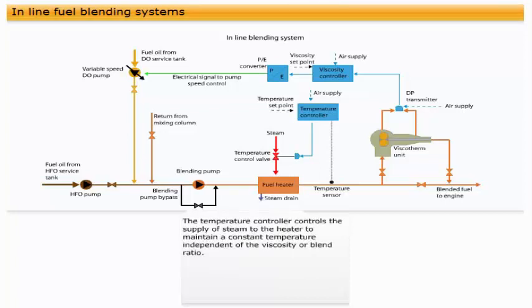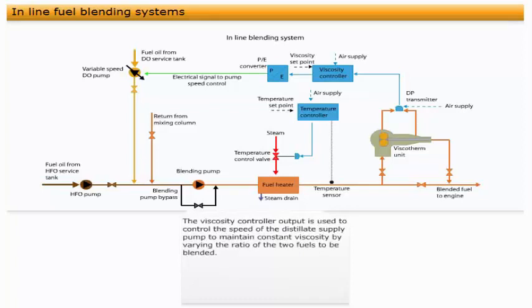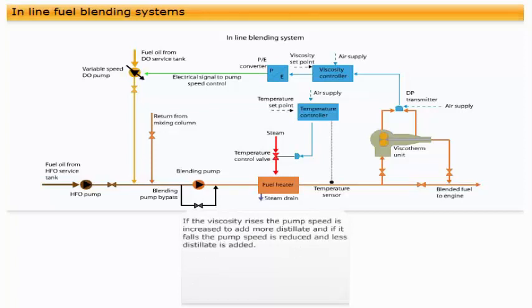The temperature controller controls the supply of steam to the heater to maintain a constant temperature independent of the viscosity or blend ratio. The viscosity controller output is used to control the speed of the distillate supply pump to maintain constant viscosity by varying the ratio of the two fuels to be blended.